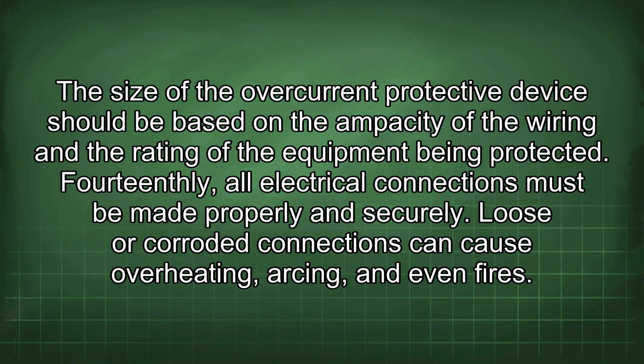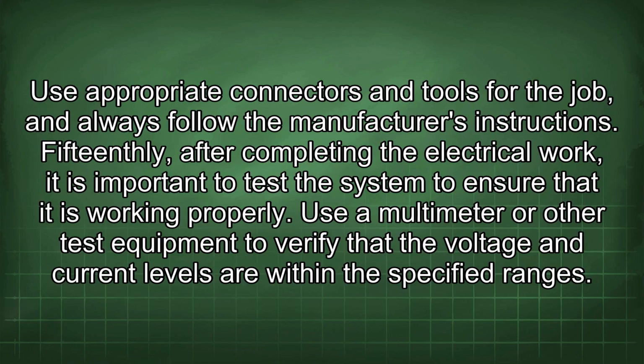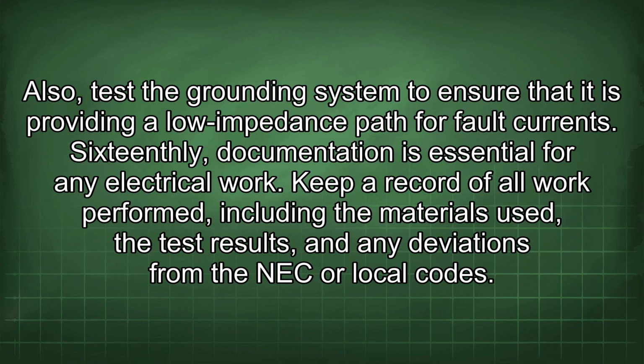Loose or corroded connections can cause overheating, arcing, and even fires. Use appropriate connectors and tools for the job, and always follow the manufacturer's instructions. 15th, after completing the electrical work, it is important to test the system to ensure that it is working properly. Use a multimeter or other test equipment to verify that the voltage and current levels are within the specified ranges. Also, test the grounding system to ensure that it is providing a low impedance path for fault currents.